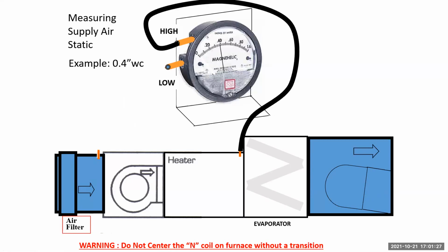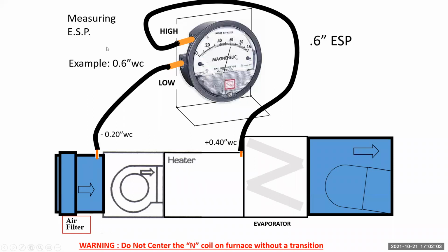That's your return. Here's your supply. After your furnace, I know it looks like it's inside the furnace, which it actually is. Best thing to do, if you can access the back of the furnace, get in the center of the furnace, about 2 inches down from the top lip of that furnace, drill a hole, you're right there. If you have to do it from a side, do it from a side, but if we can get in the center, better. If we can't, it is what it is, but no more than about 1/8 of an inch inside there, unless you have pitot tubes, and we'll go over that in a second. But our return was 0.2. Our supply, we're at 0.4. 0.2, 0.4 equals 0.6.